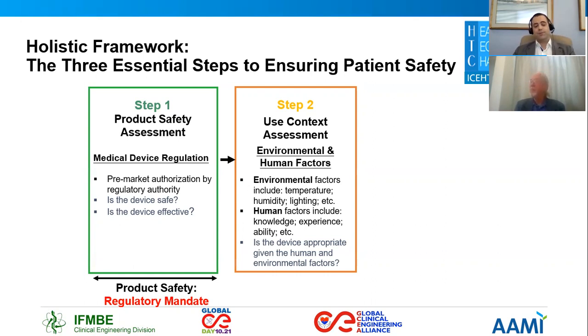At step 2, a user must proceed to consider the specifications of the marketed device and examine the range of environmental and human factors and conditions under which the device was designed to be used. These factors include the quality and condition and suitability of the physical environments in which the medical devices are going to be used. Following this assessment, the user must then decide whether the marketed product is still safe given the user's environment and human factor conditions.